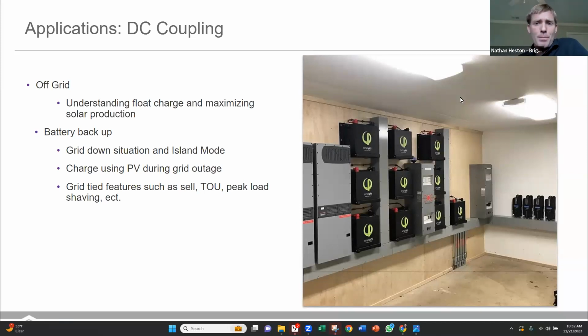Applications for DC coupling: if you're off grid, certainly DC coupling makes the most sense. You don't have a grid there to feed back to. So understanding what settings need to be made for your off-grid system is important. You'll want to know our float settings. What is our float voltage, Daniel, for our batteries? 54 volts. 54.0 volts, and our bulk setting on our batteries is 56 volts.